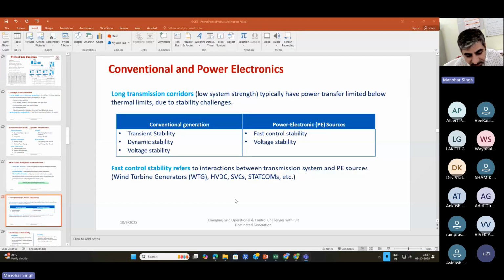In traditional cases, I have inertia. Whenever a disturbance comes, it is the synchronous machine which absorbs the disturbance for some time. But these resources are very fast, so it's difficult to handle, and otherwise they will immediately trip. So we require very fast stability control devices, like STATCOM, SVCs, or HVDC type systems, which can interact with the system in very little time. So these are the technologies these machineries are getting equipped with.